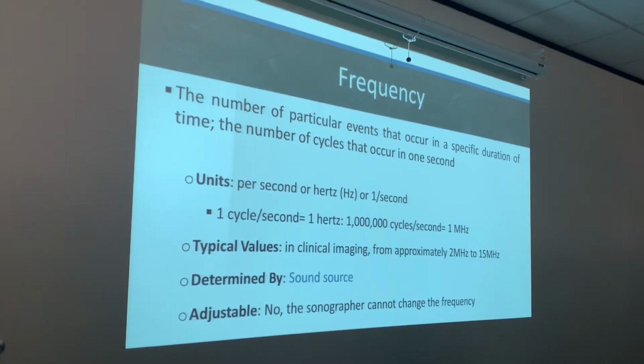So just think about our transducer. We have that C5 transducer. The C5, that means there are going to be 5 million cycles per second. That's why I'm telling you, ultrasound is happening so fast. Just think about when you're doing an ultrasound, how do you think it's able to look like it's recording live, right? The ultrasound sound waves are happening so rapidly that you can't even see that it takes time when you're moving, but it does. And you notice that when you start adding more and more applications onto your screen, because it'll slow down.